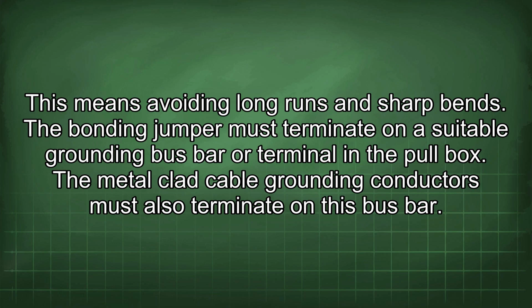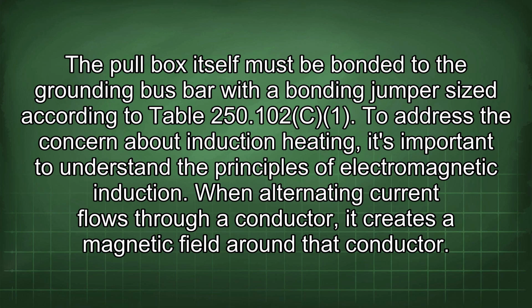The bonding jumper must terminate on a suitable grounding bus bar or terminal in the pull box. The metal-clad cable grounding conductors must also terminate on this bus bar. The pull box itself must be bonded to the grounding bus bar with a bonding jumper sized according to Table 250.102(C)(1). To address the concern about induction heating, it's important to understand the principles of electromagnetic induction.